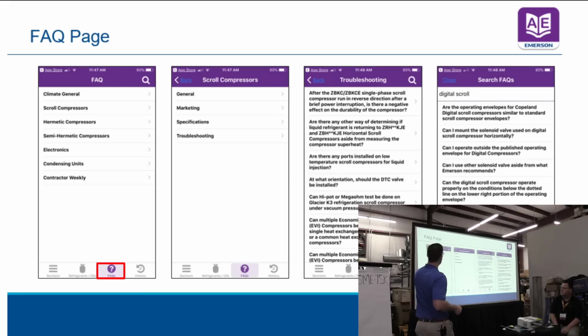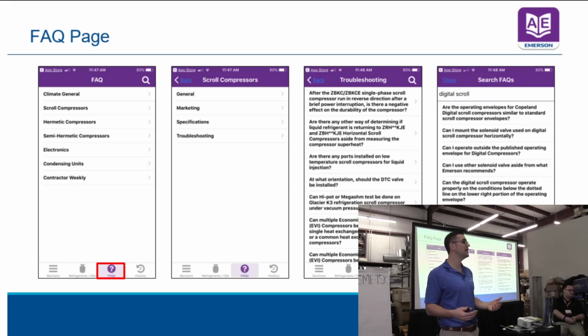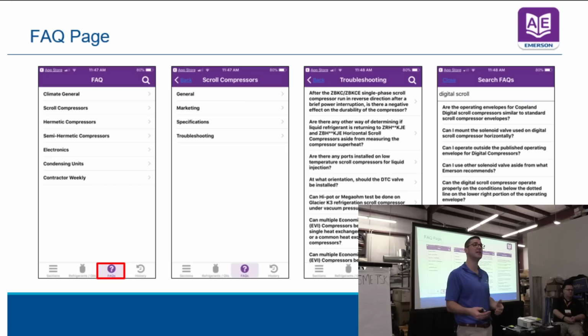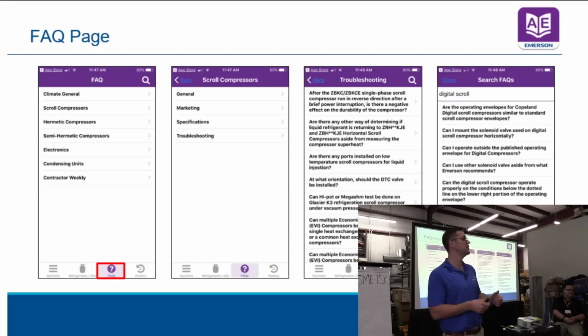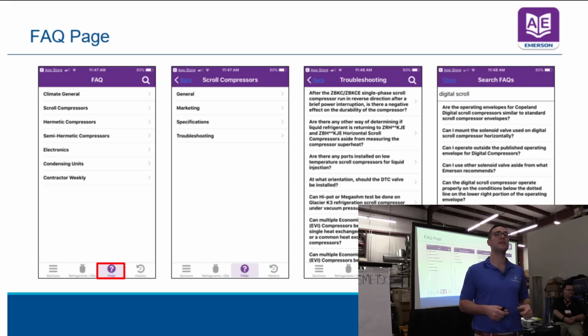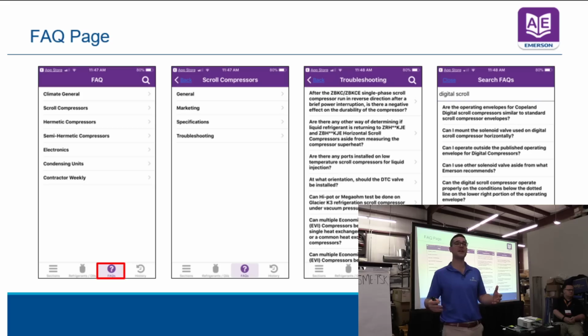Okay, the FAQ page. This one's really important, like Don just talked about. In this FAQ, you can go in here and write superheat, and it'll tell you what superheat is: evaporator superheat, system superheat. Is there any other way to find out if the compressor is flooding back or has liquid dilution? Yes, look it up. It's super cool. Demand cooling, liquid injection, or EVI, enhanced vapor injection. You don't understand that stuff? Press it here and find it.